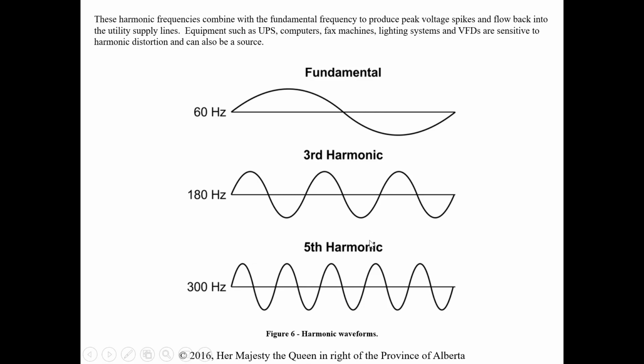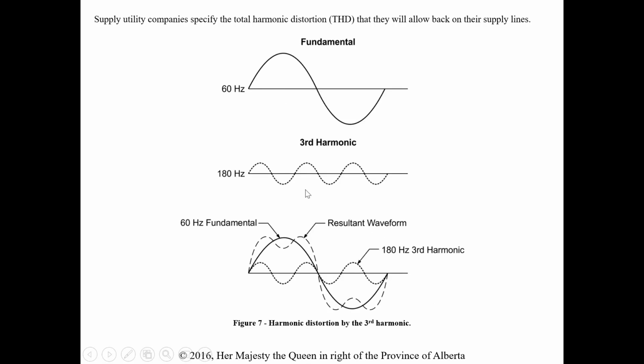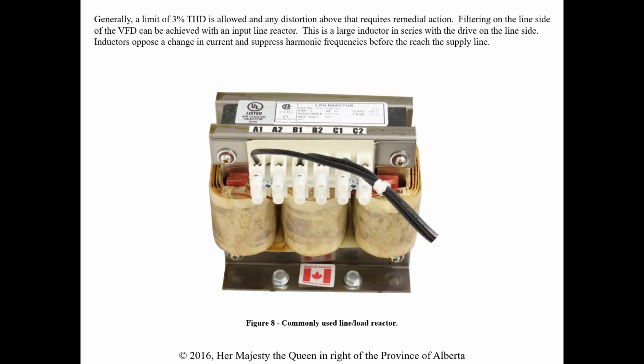Okay, but we're getting these frequencies that are going to start affecting our waveforms, and we definitely don't want that. So the supply utility actually specifies the total harmonic distortion that they will allow back on their supply lines. So if you buy a VFD, I assume that the line and load reactors are already installed and would be within these ranges. So they say generally a limit of 3% total harmonic distortion is allowed, and any distortion above that requires remedial action.